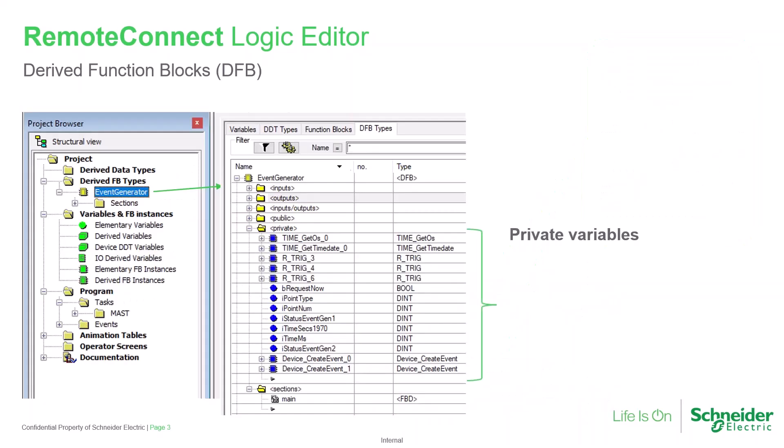As a derived function block is developed, it will most likely include private variables. These are commonly known as local variables, meaning that they're hidden from the logic outside the function block itself. In this way, a private variable in one instance of a DFB won't interact with the same variable in another instance.